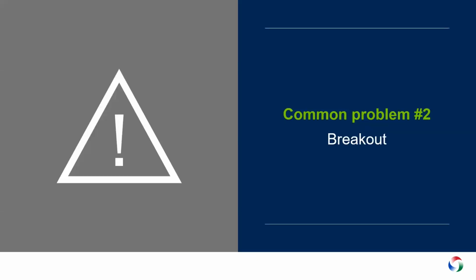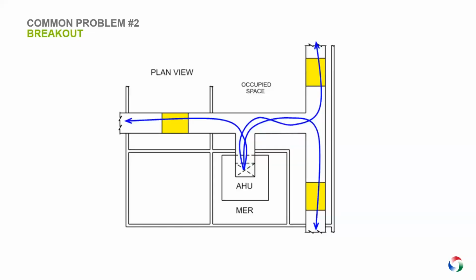And now I want to talk about the common problem number 2, which is breakout noise issue. To explain that, let's assume we have an air handling unit in this mechanical room, which is creating noise to this occupied space. So these 3 yellow boxes are 3-stage silencers we have in every single branch to mitigate the noise. But we will still have the noise issue because the noise source in this case is this air handling unit, which is creating the noise issue in this area, which is called a breakout noise issue. So basically the noise is breaking out from the duct itself going into this occupied space.